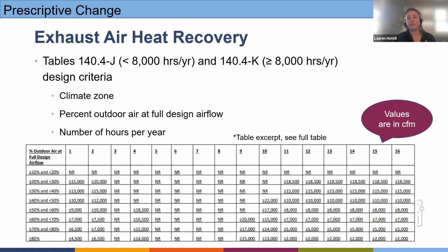The table values that you see below are again another excerpt. It's quite a long table. The values are listed in CFM, and they are dependent on climate zone and percent of outdoor air at full design airflow, as well as number of hours per year. Depending on the hours per year, you'll go to either table J or table K for your design criteria. Compliance is also triggered if a decoupled dedicated outdoor air system is utilizing the exhaust air heat recovery to avoid economizer requirements. So make sure you're keeping an eye on that if you do end up applying for that exemption.